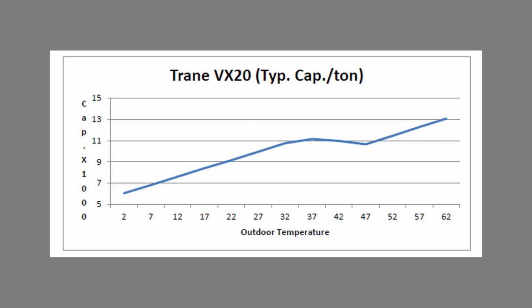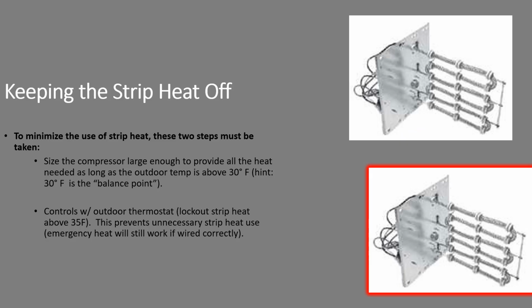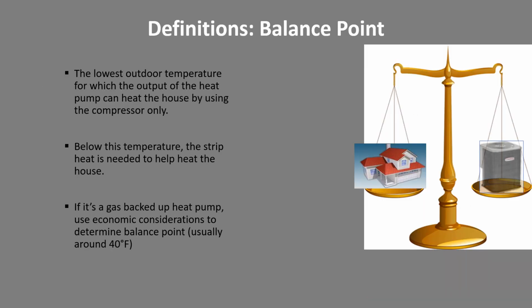This is another extended capacity or cold climate heat pump. You've got this nice flat performance curve between 47 and roughly 32. And in the Northwest, we spend a lot of our hours in that temperature range. Keeping that strip heat off, well, we have to have controls, and we also have to have the ability to heat the house using the compressor only down to 30 degrees. Balance point.